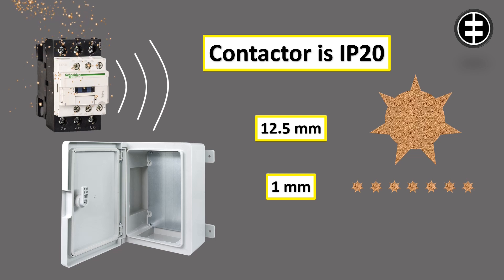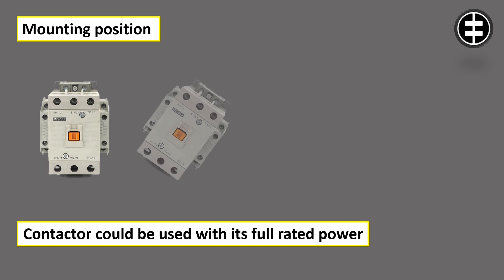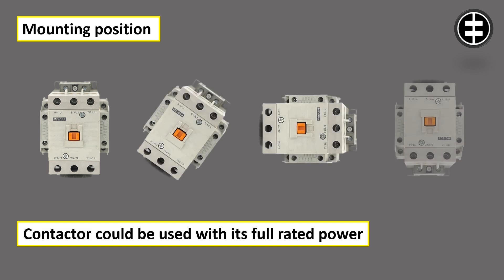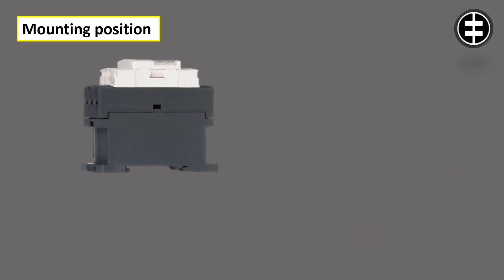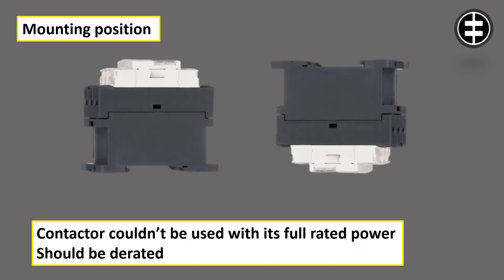Mounting position could also be the reason. These positions are permissible without derating, but if the contactor position was one of those positions, it must be derated. For the derating percentage, check the contactor datasheet.